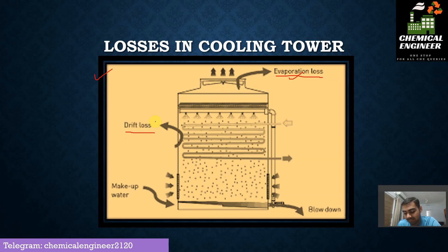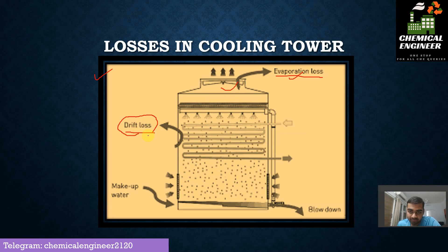The second type of loss is drift loss. Drift means something that is moved using a force. In a cooling tower, water is carried away by the force of the impeller or by striking curved surfaces, and is thus carried out of the cooling tower — these losses are known as drift losses. The third type is blowdown loss, which is related to the quality parameters of the water flowing through the cooling tower. We will cover blowdown in detail in the next video.